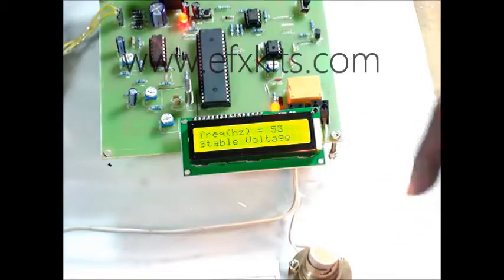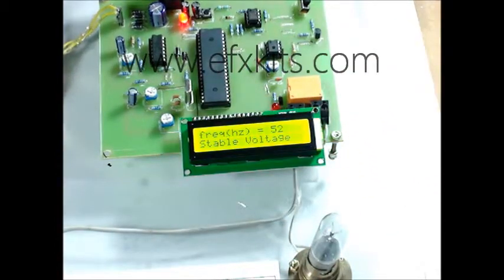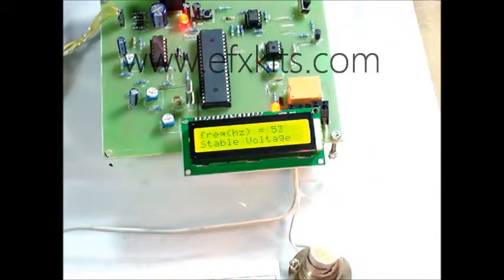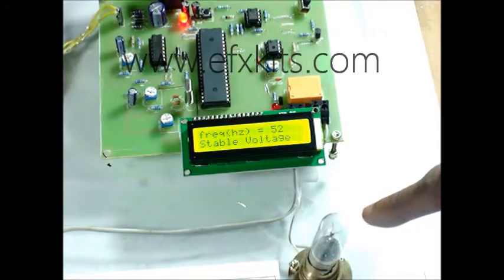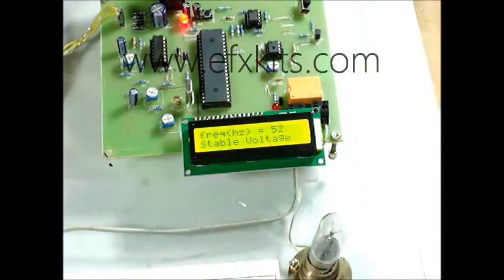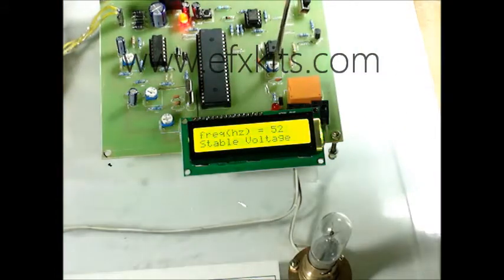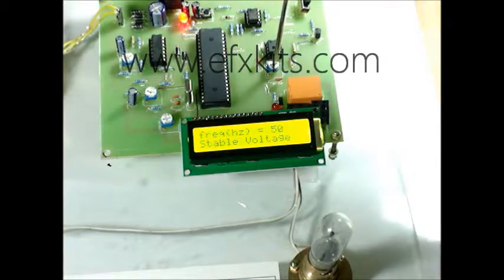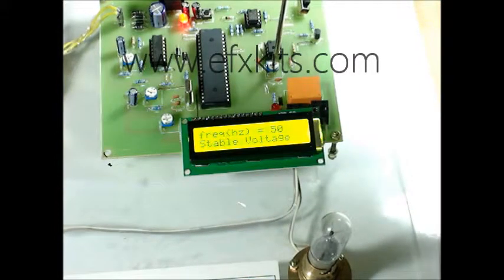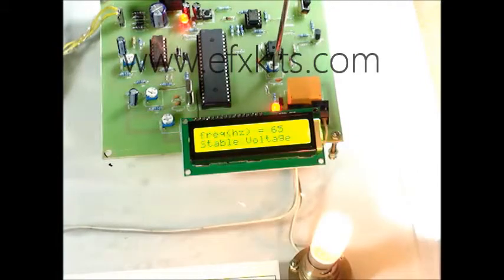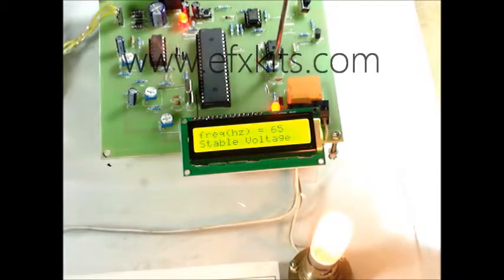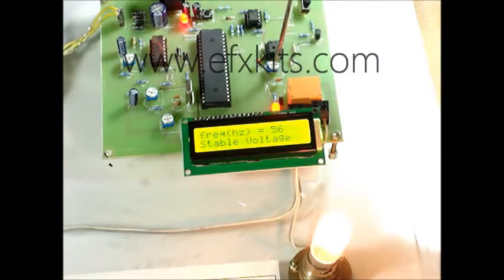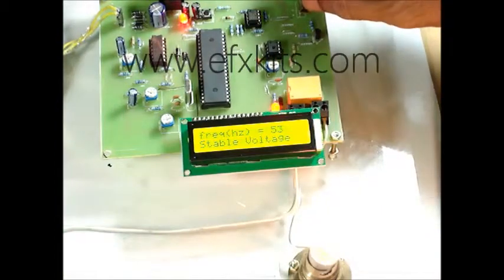Islanding means it will disconnect. Now when it crosses more than 52 and goes to 53, it indicates that islanding has happened when it goes to 53. Now I can vary this frequency here. Now if I go to this side, it remains steady. If I go to this side, now the frequency goes high, because the frequency goes high and the islanding takes place. So that is what is the frequency part.